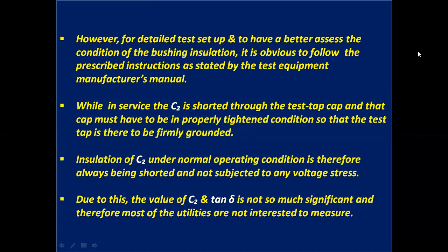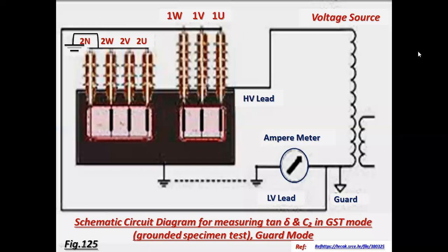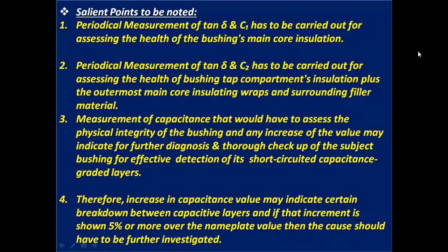Due to this, the value of C2 and tan delta is not so significant, and therefore most of the utilities are not interested in measuring it. Now see the diagram that is in GST GUARD mode. Salient points to be noted.